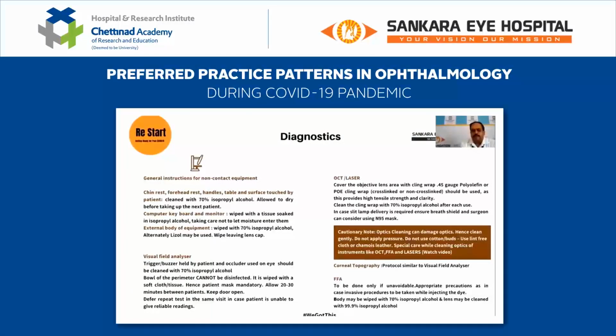When it comes to specific equipment, for an HFA, except for the inside of the dome, the rest of the outside can be cleaned with 70% isopropyl alcohol. None of the manufacturers are telling us how to clean the inside of the dome, which means it becomes critical for the patient to wear a mask whenever you're doing any visual field examination. Between two patients, it is good to give about 20 odd minutes to allow any aerosols to settle down, because you really cannot clean the inside of the dome. Again, keep the door open so that it is ventilated. Generally, our HFA rooms are very small rooms, so as far as possible, keep it open. If a repeat test is required, defer it if the patient is not able to give any reliable readings.